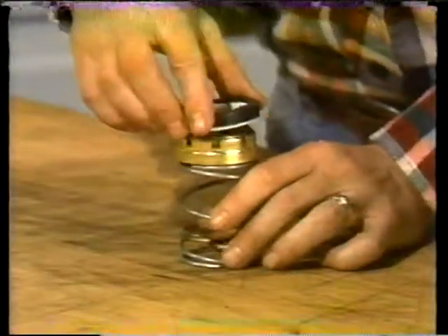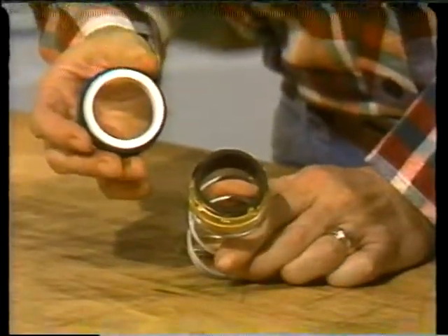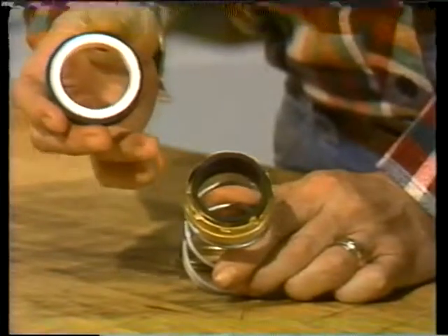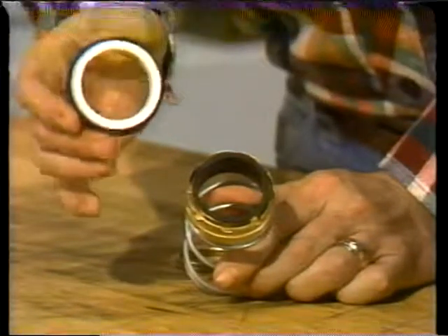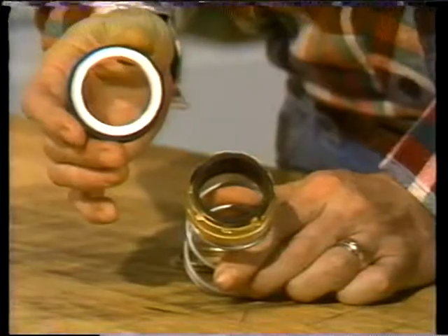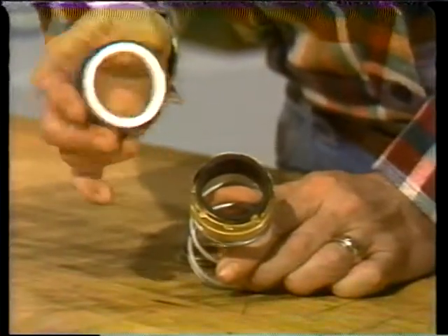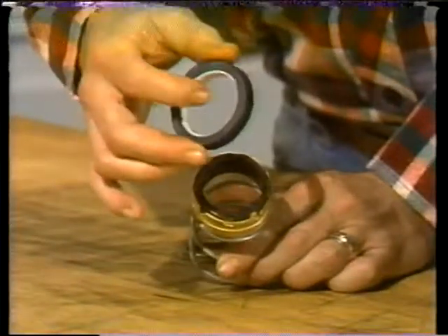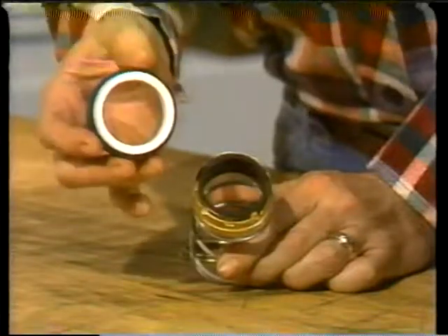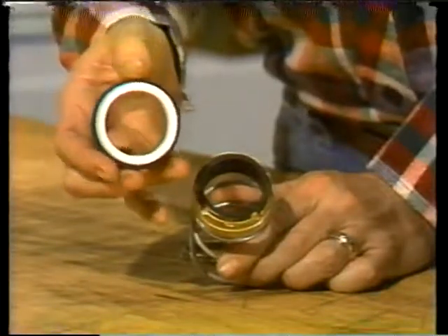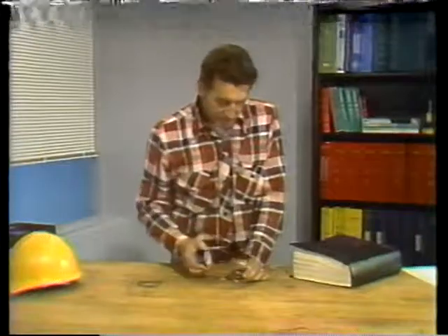Now, mechanical seals are one area where you can't compromise. If one of the faces on a mechanical seal needs replacing, both faces must be replaced. The two faces wear together during operation, and a new face is not going to seat properly against the old one. All right, one more consideration when you're replacing parts. Keep the new part clean. Dirt introduced during maintenance work is one of the major causes of machine damage.